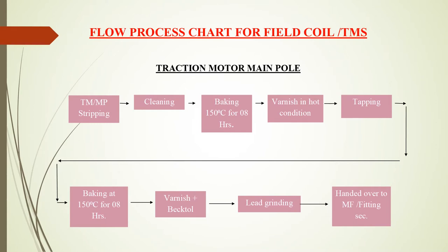After being stripped from the magnet frame, both main pole and inter pole are brought to the field coil section for overhauling. For the main pole: initially, main pole stripping takes place where old tape is removed and mica and glass tapes are removed using a knife. Then the cleaning process takes place where carbon particles are cleaned using Orion 77. Thereafter, baking at 150 degrees Celsius for 8 hours is done, followed by applying varnish H71 in hot condition.